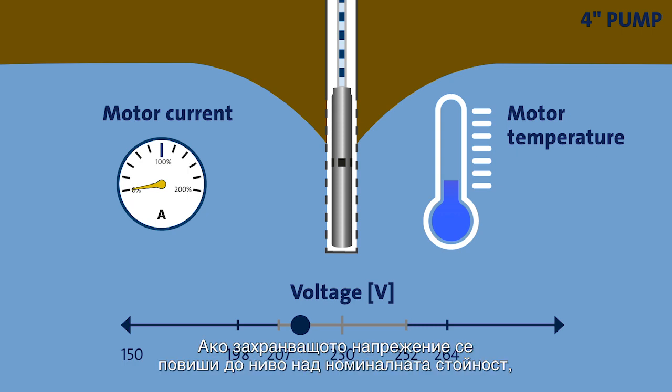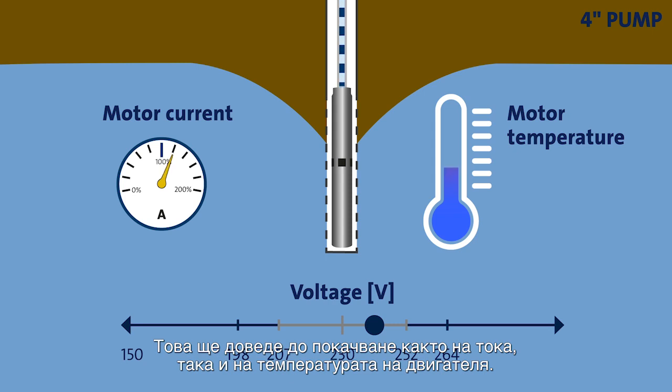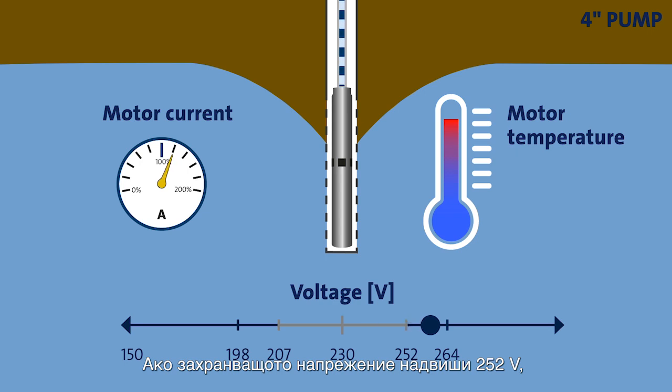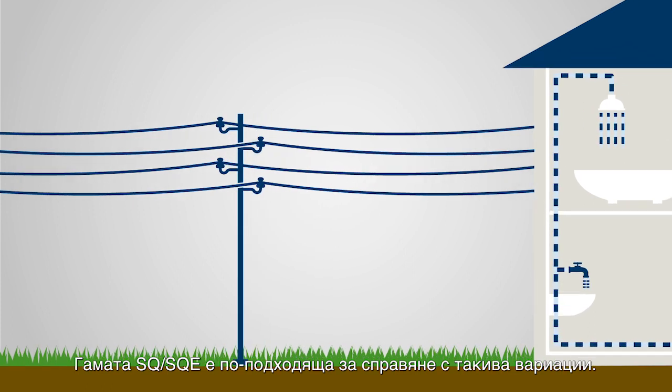If the supply voltage increases to a level above the nominal value, the motor speed and as a result the load will increase as well. This will cause both motor current and motor temperature to go up. If the supply voltage exceeds 252 volts, the motor protector will stop the pump. The SQ and SQE range is better suited to handle such variations.